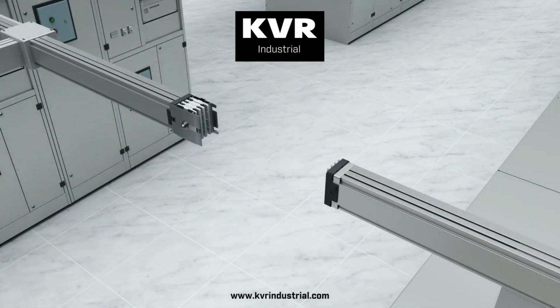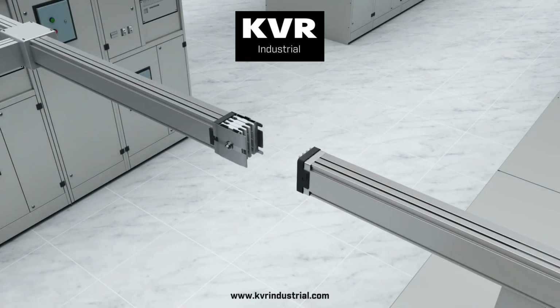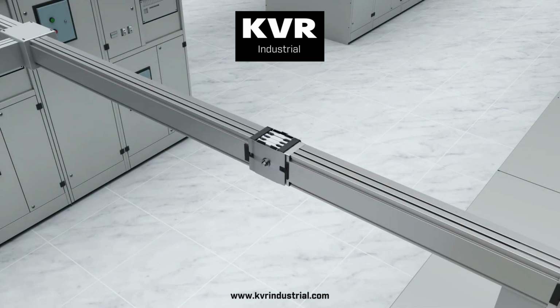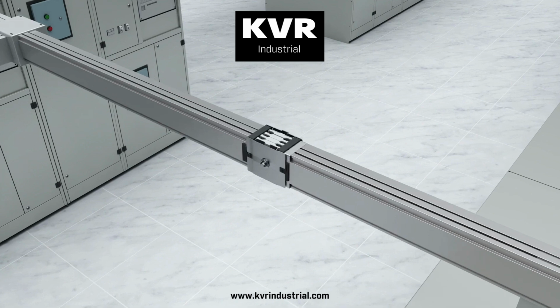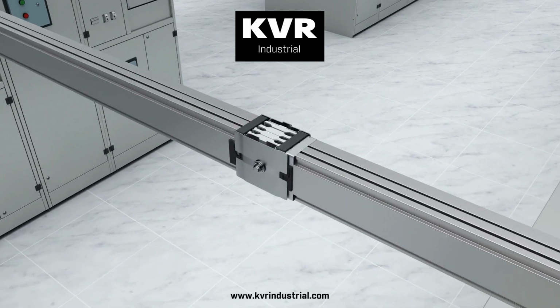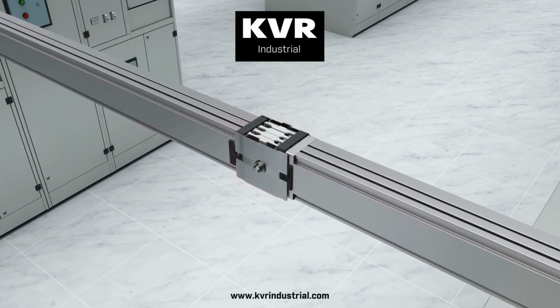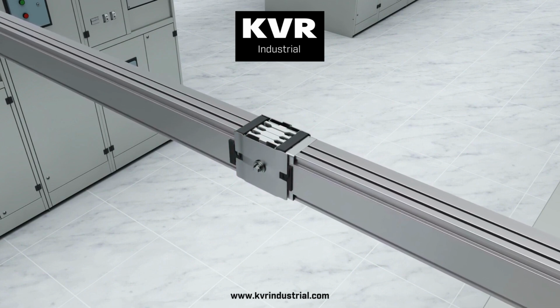With all electrical assets, joints are typically the weak spots where faults occur, resulting in outages. The bus duct is heavy. The effect of gravity, constant heating and cooling, and movement from vibration or seismic activity will distort and compromise joints.